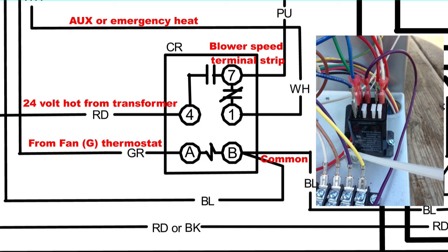If you have a call for the heat strips and you don't have a call for fan, then it will travel directly to the number 1 terminal. Since it's normally closed, it travels to number 7 and then out the purple wire to the speed tap. So it's just like a fail-safe that's very similar to the six-pin relays shown in the past. The infamous Goodman blower relay and the infamous Goodman blower relay strikes again are both videos on the Talyn 875 channel (T-A-L-Y-N 875). Same idea, just a little different way going about it—uses low voltage instead.